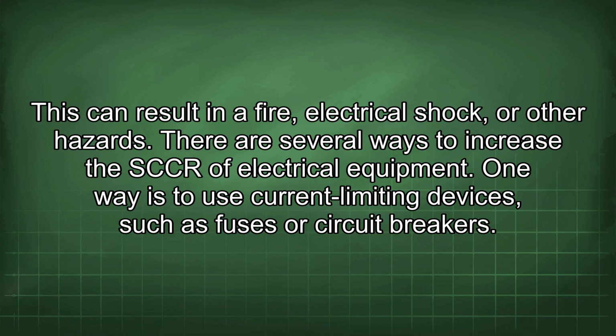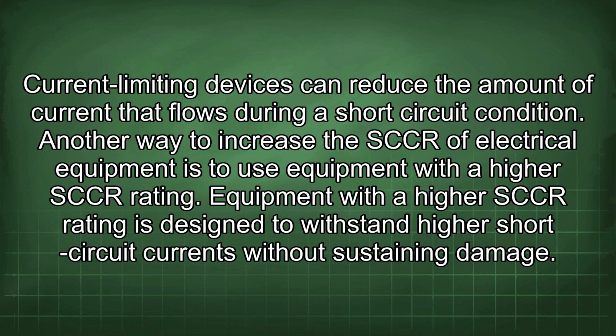There are several ways to increase the SCCR of electrical equipment. One way is to use current limiting devices, such as fuses or circuit breakers. Current limiting devices can reduce the amount of current that flows during a short circuit condition. Another way to increase the SCCR of electrical equipment is to use equipment with a higher SCCR rating. Equipment with a higher SCCR rating is designed to withstand higher short circuit currents without sustaining damage.